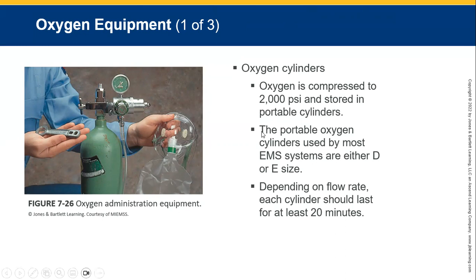Oxygen. Let's have a look at oxygen quickly. Oxygen cylinders are compressed to around 2,000 pounds per square inch, which, on a side note, turns it into a missile if it becomes damaged. 2,000 pounds of pressure is a lot. Portable cylinders, size D or E, would last about 20 minutes on a high flow rate. If you need a longer period of oxygen, one would consider lessening the flow rate to increase the length of oxygen delivery.